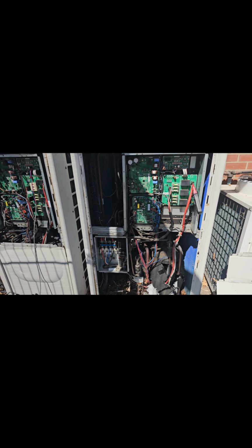I'm just waiting for the system to start up now. I've proceeded to connect our service checker. Let me go ahead and switch off this flash. We're in the daytime. Yeah, it's pretty hot inside. Room temps are about 29 degrees Celsius, 30 degrees Celsius. Some of them are 28, 27, and the lowest is 26. Ambient conditions right now, according to the sensor on the outdoor unit data, we've got an outdoor temp of 32 degrees. With my thermal hygrometer, my apologies, with my thermal hygrometer I've measured about 34, close to 36 degrees ambient.